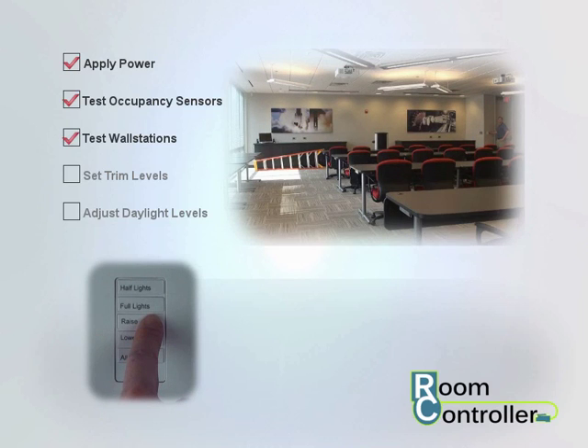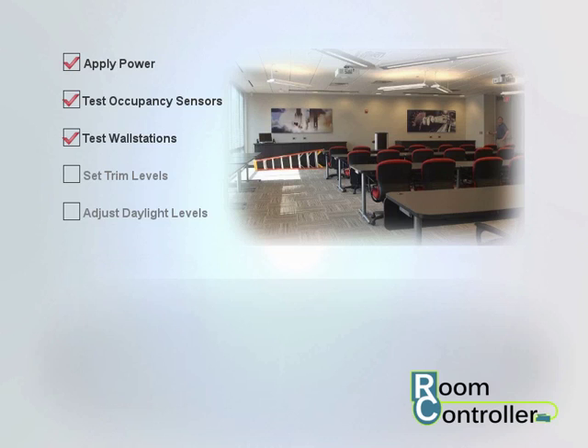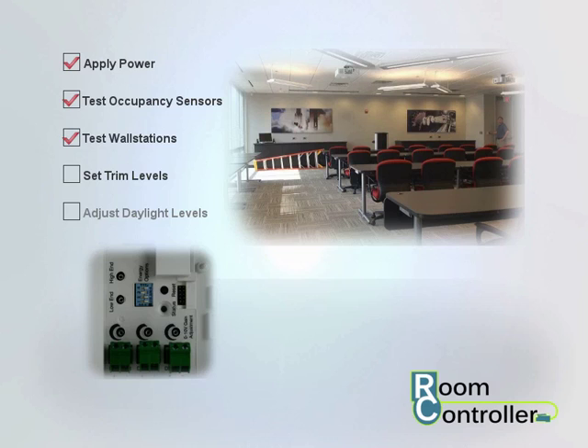Once wall station operation has been verified, if you are using 0 to 10 volt dimmable loads, set the appropriate trim level for best operation and efficiency. Trim levels have been preset to approximately 90% maximum. Additional energy savings can be gained by adjusting this further if electric light contributed is over the target illuminance for the space.